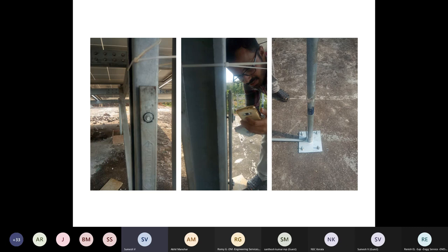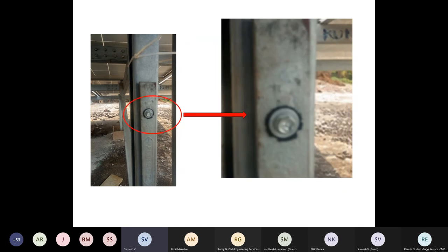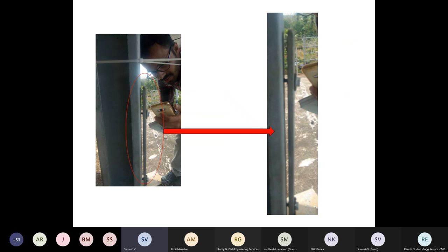But we will see each of these photos. This is the first photo. Here the person has used a screw with plastic washers. As far as earthing is concerned, it should be tight, it should be perfect, it should give minimal resistance to the main earthing system. But by using this plastic washer, that condition cannot be achieved. Then see the side view. Here you can see a very huge gap between the main structure and the earthing conductor. That means that earthing is not perfect.